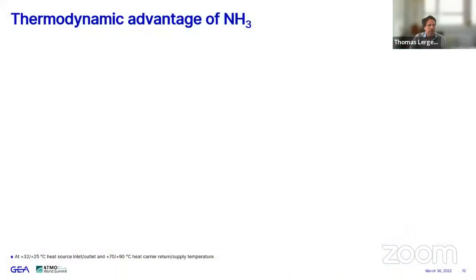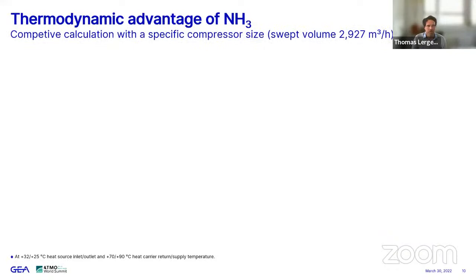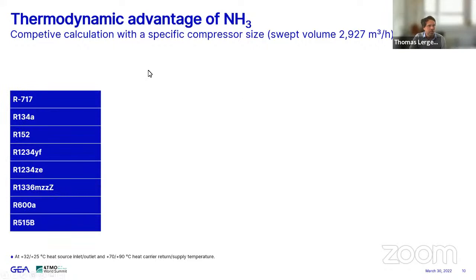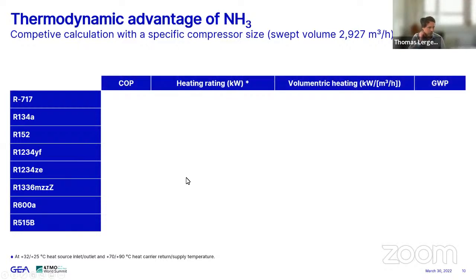Here is a calculation with a specific compressor. We took a specific compressor size of our compressors. You see the swept volume of nearly 3,000 cubic meters per hour, so it's already a large-scale compressor. And we looked at different refrigerants. Here's ammonia on top. The second one is still widely used in a lot of regions. And then there are some refrigerants that are sometimes used for heat pumps. We looked at a few figures like the efficiency expressed by the COP, the heating rating, the volumetric rating, how many kilowatts you can get per cubic meter per hour, and the global warming potential. Here are values for CO2.